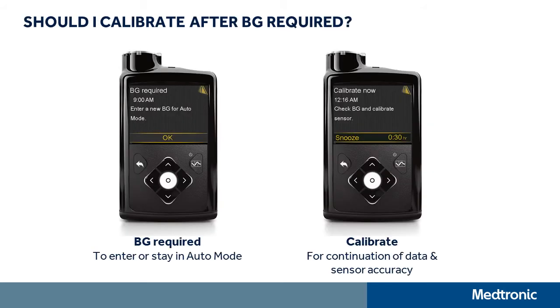You may wonder if you need to calibrate after you get a BG required alert. Just a friendly reminder, a BG required alert is to stay in auto mode. Calibrations are to ensure you continue to receive your readings and to make sure those readings are accurate. If you happen to get a BG required alert and it's also time to calibrate, go ahead and use the blood glucose for a calibration. But you do not have to calibrate every time auto mode asks you for a BG.